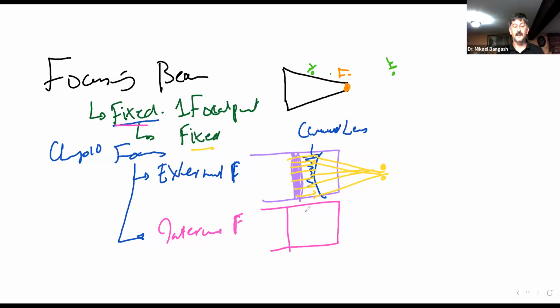Not that we had a curved lens in front of the PZT that was going to cause the beam to converge in the near zone. But actually the PZT itself has this curved surface. So as the sound rays were produced by the PZT, they hit that curved surface, and they will start to converge. And the beam will focus at a fixed point. Clear? So why are these focal points here fixed? Mainly because it is the hardware of the transducer that sets that.